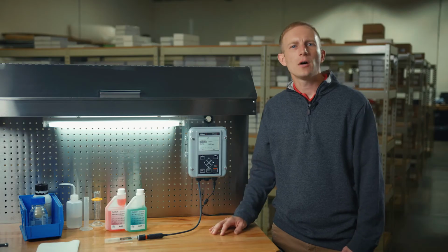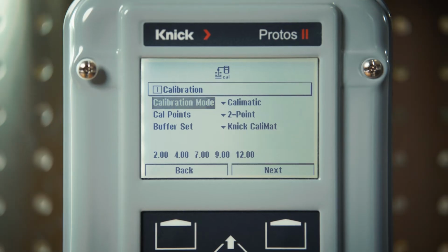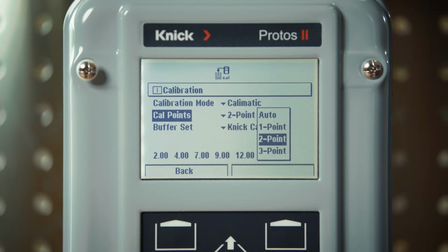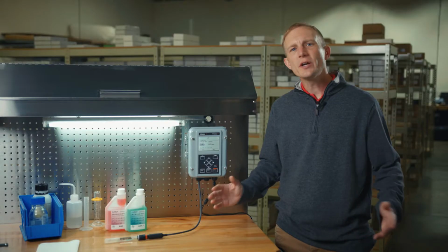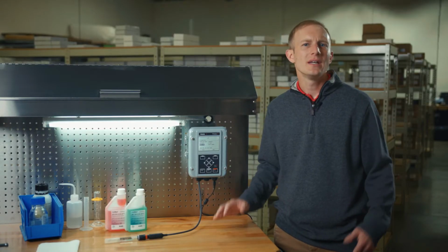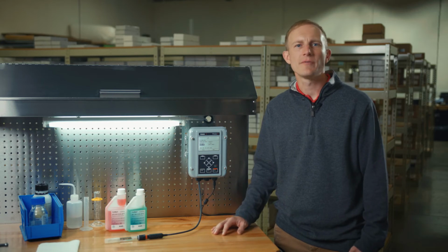Under the number of calibration points, we will select 2 point and then move on to select the buffer set. Since we are using automatic calibration, it's very important to have the proper buffer set selected in your Protos transmitter. This ensures automatic recognition of the buffer's value as well as automatic temperature compensation during the calibration process.